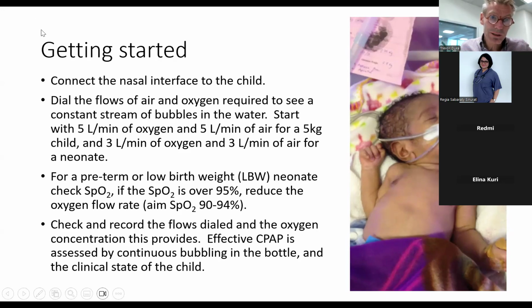You have to be able to see the bubbling. If you can't see the bubbling, then there's no CPAP being delivered. If you can see the bubbling before you attach it to the baby's face, then there's auto bubbling. So you dial the flows up until you get a steady stream of bubbling once you've connected it to the child. In an older child, of 5 kilograms or more, I usually start with 5 liters per minute of oxygen and 5 liters of air.